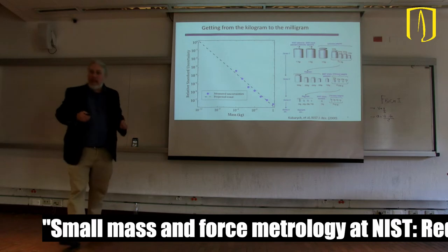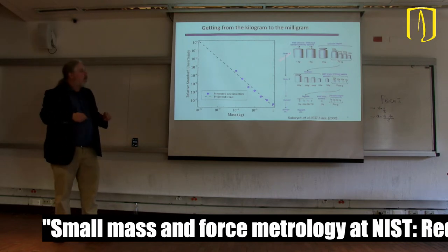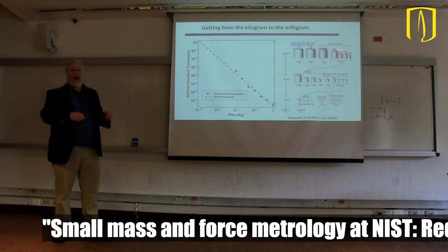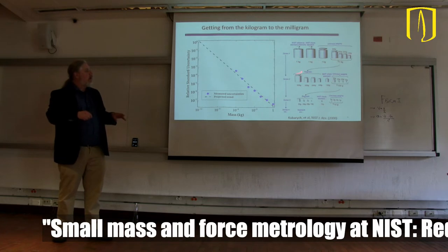So we've become very good at this process over the years. So we can do this with 5 masses at a time. And we go by decades. 1 kilogram to 100 grams.